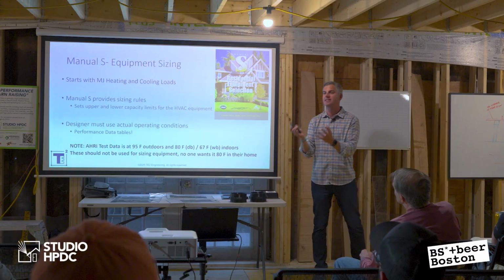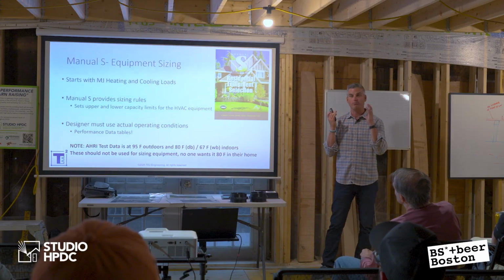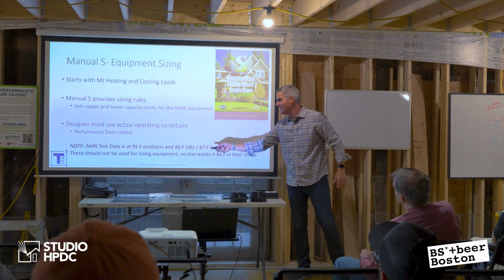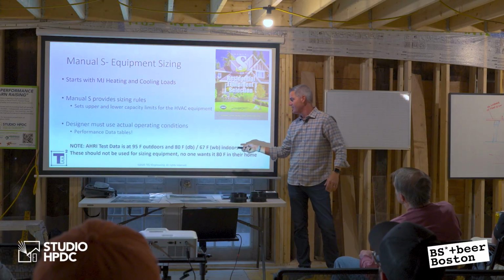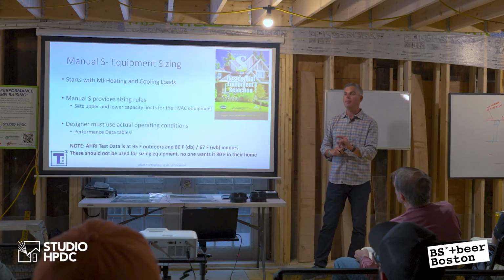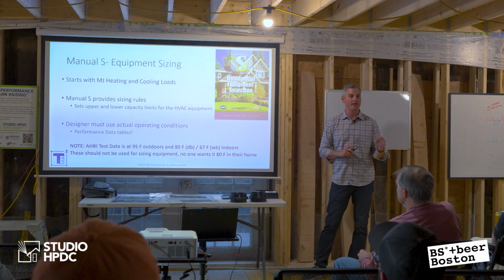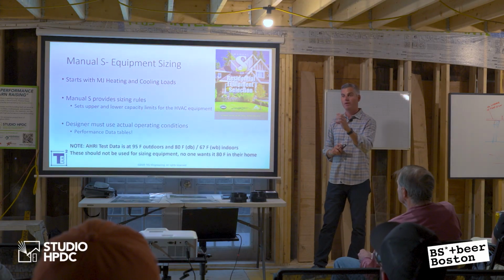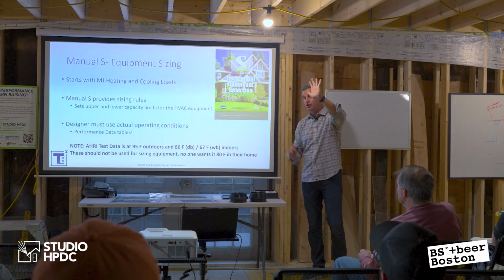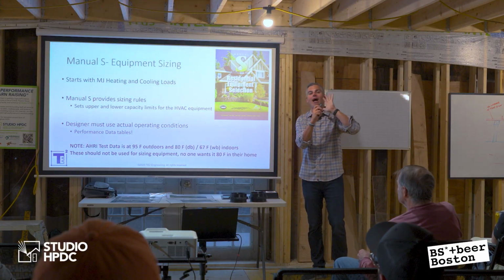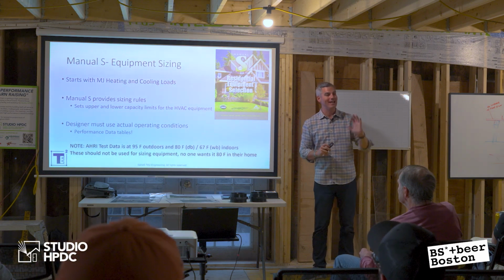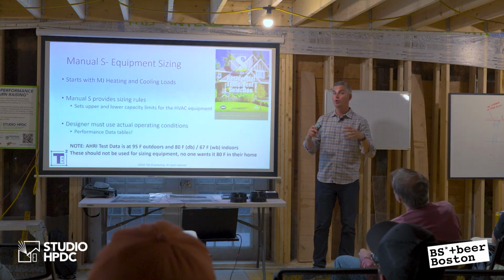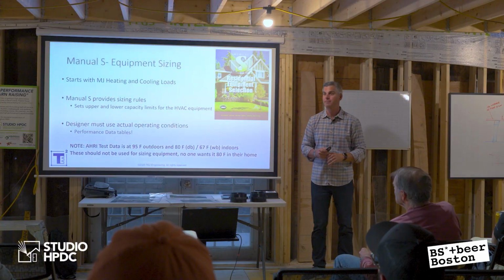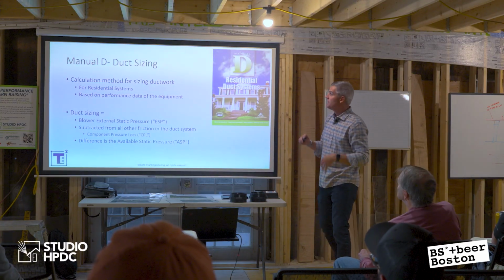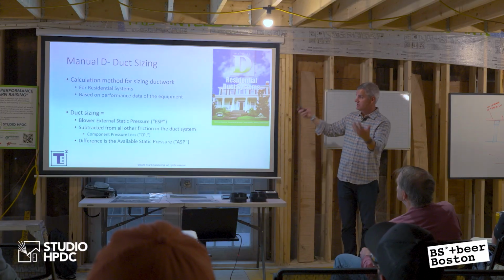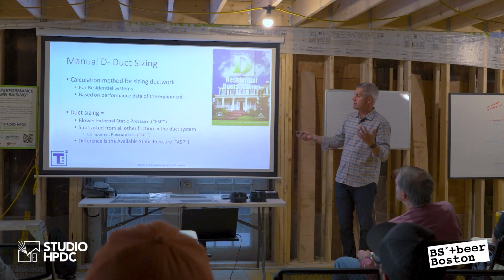AHRI data, they look at the standard data that the manufacturer publishes. The standard data is at 95 degrees outside and 80 degrees inside with a 67 wet bulb. I don't know how many people live inside their house with an 80 degree set point in cooling. But that's what the data is. When you see the sales literature, that's what's published. That's not reality. So you have to go to the performance data tables for that HVAC equipment to give you what I'll call the real life cooling capacity for that equipment. Okay? Then you also have to do a Manual D, which is a duct design, of course, if it's a ducted system, right? And it's just a calculation method.